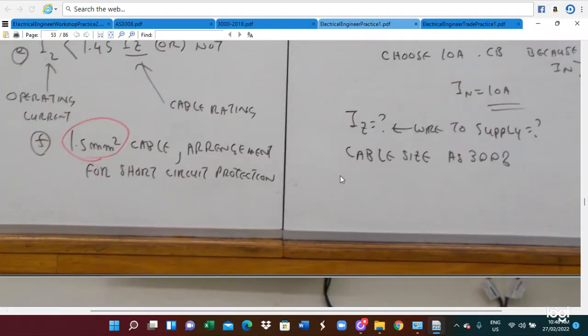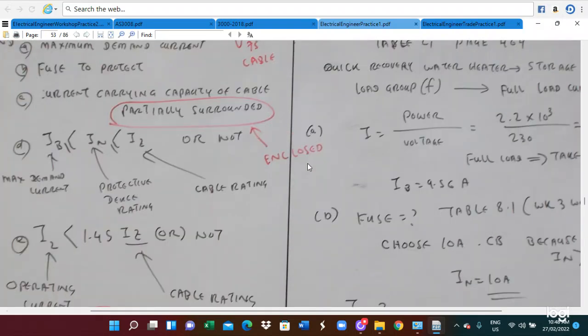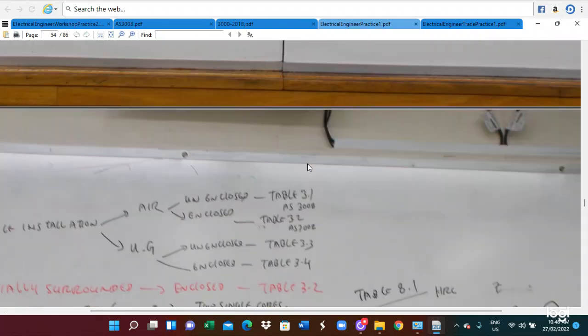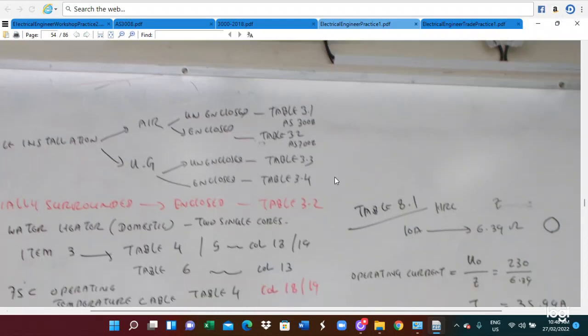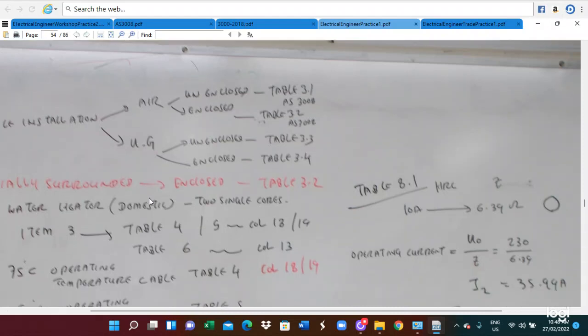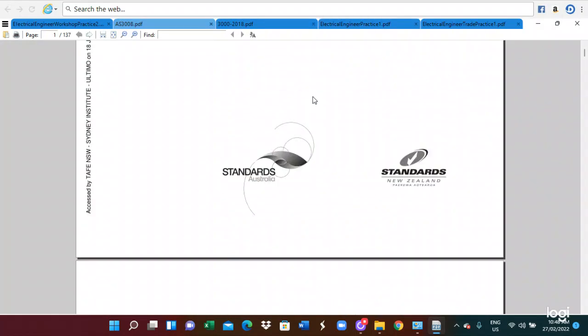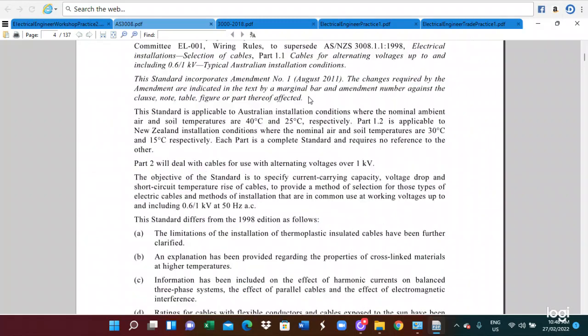The cable is partially surrounded by insulation, which means it is enclosed. Since this is a domestic water heater installation using two single core cables, and the cable is partially surrounded by insulation, we refer to Table 3.2 of AS3008 and select item number 3 for two single core cables partially surrounded by insulation.